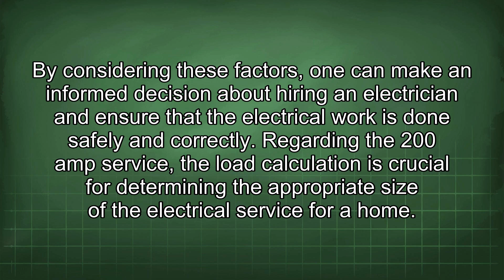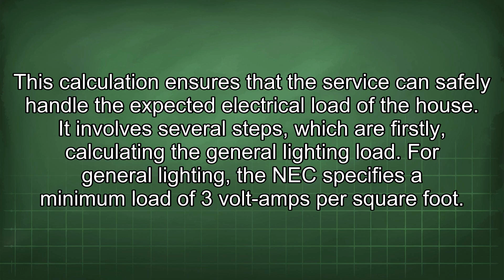Regarding the 200 amp service, the load calculation is crucial for determining the appropriate size of the electrical service for a home. This calculation ensures that the service can safely handle the expected electrical load of the house. It involves several steps, which are, firstly, calculating the general lighting load. For general lighting, the NEC specifies a minimum load of 3 volt-amps per square foot. Calculate the square footage of the house, excluding unfinished basements, garages, and attics. Multiply the square footage by 3 volt-amps per square foot to determine the general lighting load.